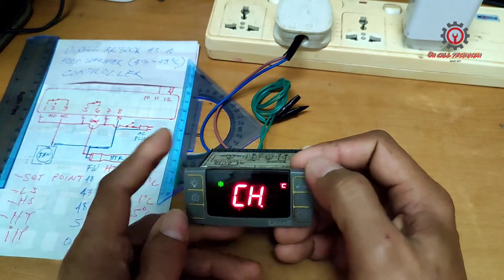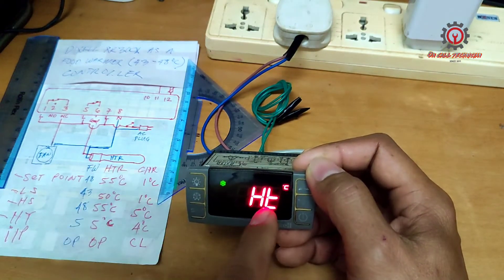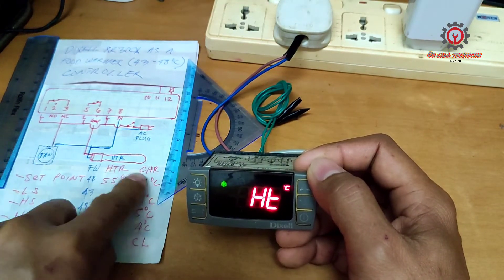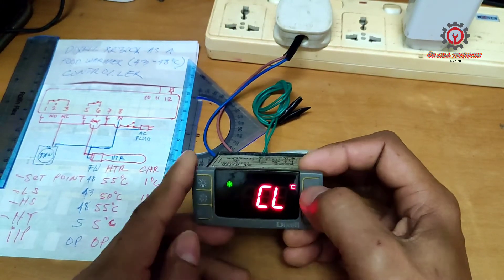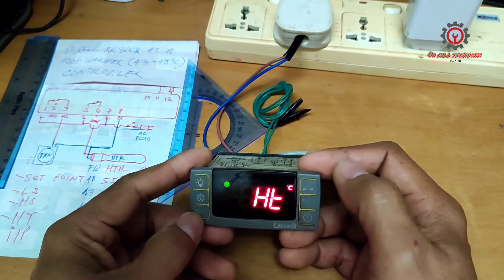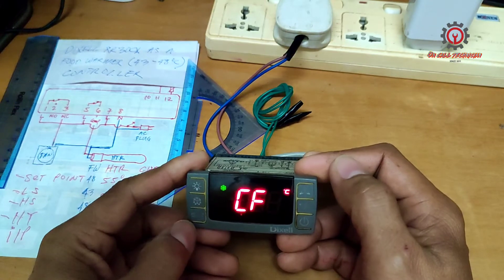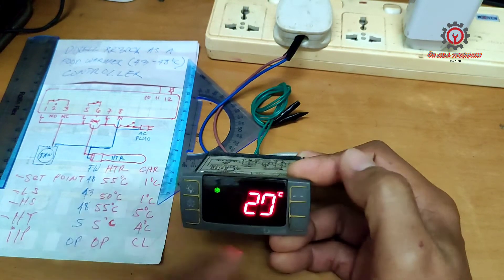There is another important parameter to change here: the CH parameter. It should be set to HTR. In chiller mode it is CL meaning cooling, but for heating purposes just change CL to HT. Then press Set and the Up button to return to the display setting.